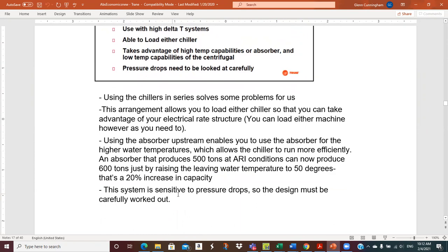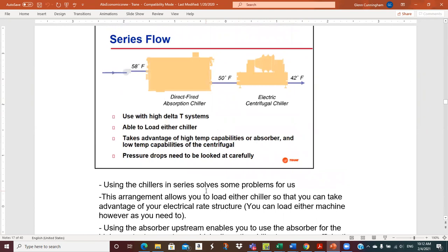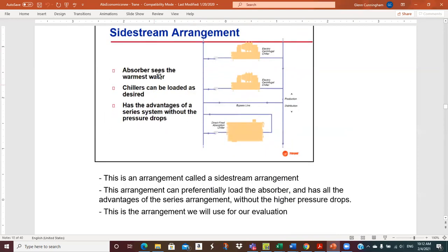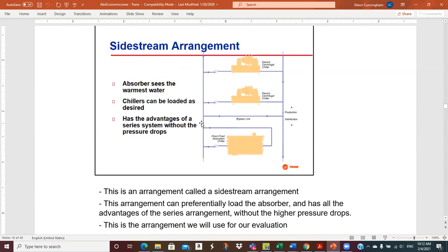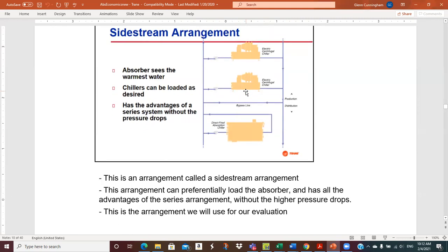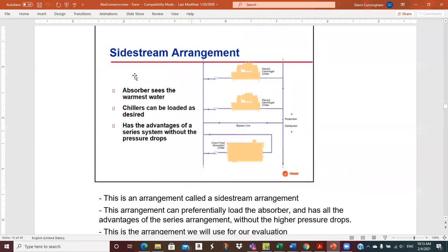So, and then it just says the system is sensitive to pressure drops, and we already talked about that. Side stream arrangement. So what you do is, here's your return water coming back. And so you're much more flexible. If we want to put the warmest water into the absorber, we can do that, make it as cold as the absorber can make it. And then if that's cold enough, we can go through the bypass line and go right back out to our system. If that's not cold enough, then we can take that water that's been cooled partially and run it through either one of these centrifugal machines and make it as cold as we need to make it. So it's certainly more flexible. So this is the one that they're going to use in the evaluation here. So that's called the side stream arrangement.